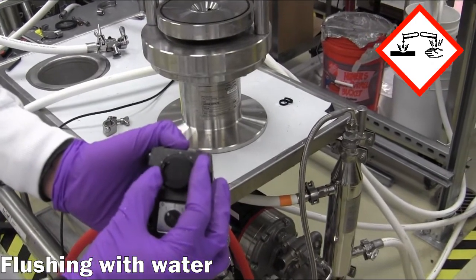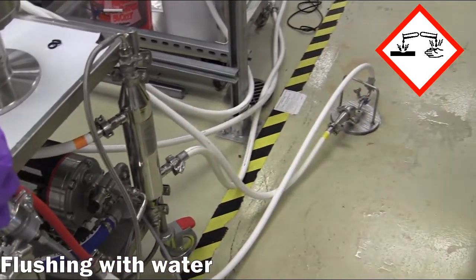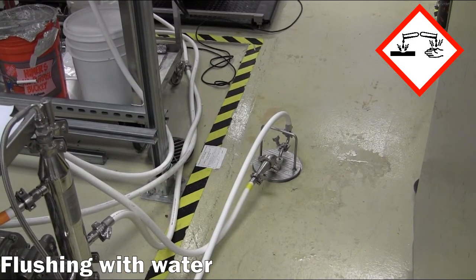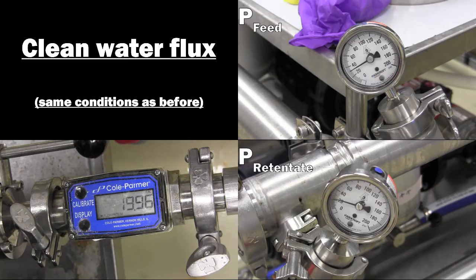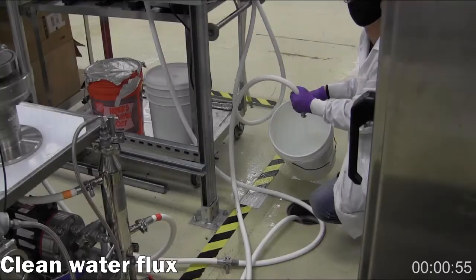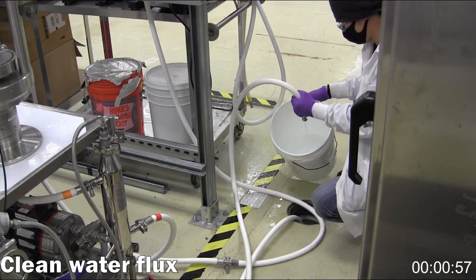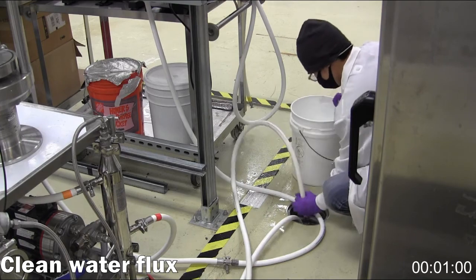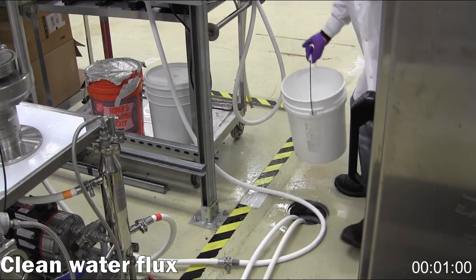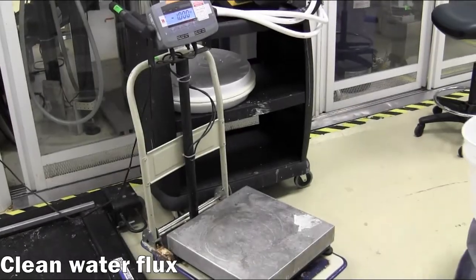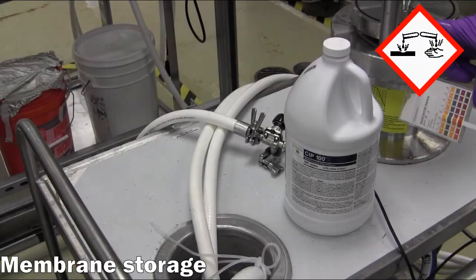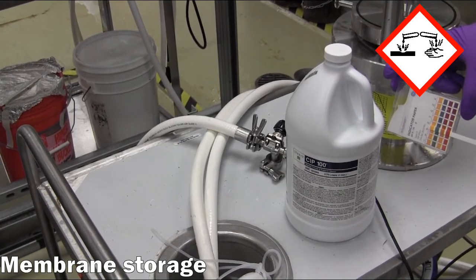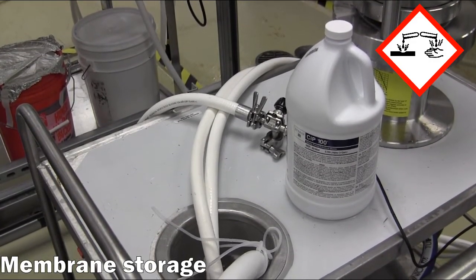Now the permeate and retentate lines are routed to the floor drain manifold and fresh water is introduced to the feed bucket. The system will continue flushing with fresh water until a neutral pH is reached on the permeate outlet stream. Lastly, the clean water flux is measured in the same manner as before the processing. The end value should be similar to the original value, thereby validating that the membrane has been thoroughly cleaned and may be reused in future applications. The membrane is typically stored in a pH 9 solution that can be made using CIP100.